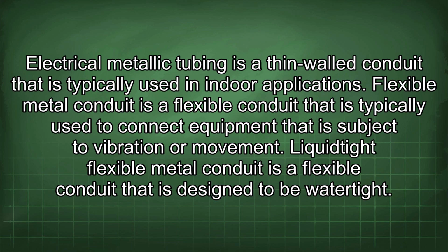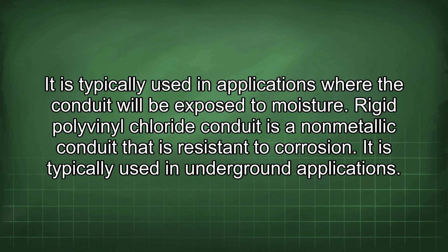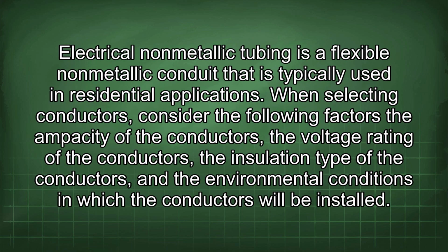Liquidtight flexible metal conduit is a flexible conduit that is designed to be watertight. It is typically used in applications where the conduit will be exposed to moisture. Rigid polyvinyl chloride conduit is a non-metallic conduit that is resistant to corrosion. It is typically used in underground applications. Electrical non-metallic tubing is a flexible non-metallic conduit that is typically used in residential applications.